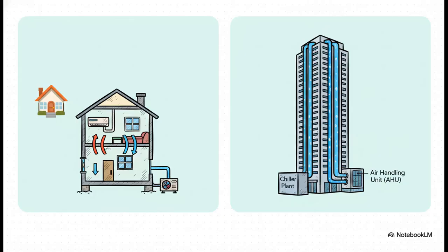So let's just put them side by side. Your home unit uses that refrigerant directly in the coils to soak up heat. But a massive commercial AHU often uses a different tactic. There's a central plant called a chiller that makes tons and tons of ice-cold water. That water then gets pumped up to the AHU's coils, and that's what cools the air for the whole building. Same principle, just a massively different scale.